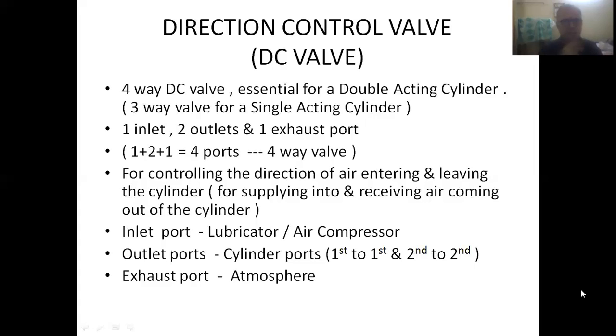And here we can see the connections. Inlet port is connected to the pipeline coming from the lubricator. First outlet is connected to the first port of the cylinder, and second outlet is connected to the second port of the cylinder. And exhaust is connected to the pipeline that is entering into the atmosphere. So friends, these are the connections to be made so far as DC valve is concerned.